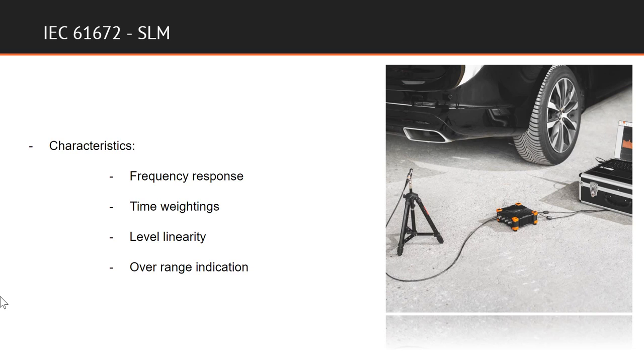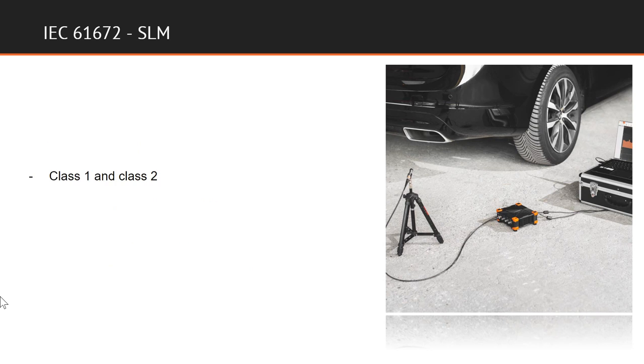Some examples of characteristics that are tested include frequency response of both microphone and filter, the time weightings, level linearity, overrange indication, and additional parameters. Sound level meters are divided into different classes of accuracy, where Class 1 is intended for precision measurements and Class 2 for simple measurements. Approximate accuracy for a sound level meter of Class 1 is 1 dB, and for Class 2, the accuracy is 2 dB.